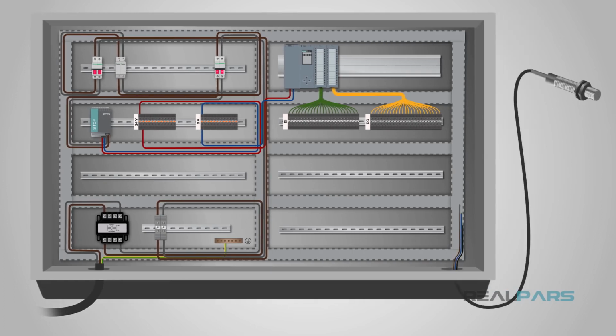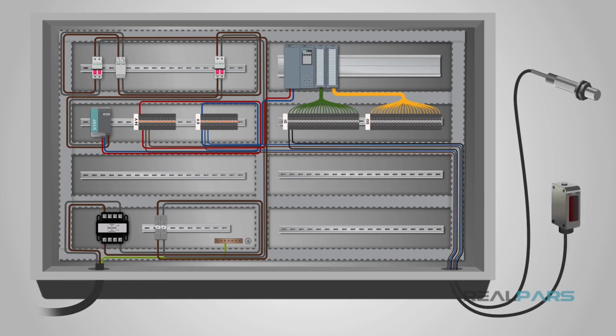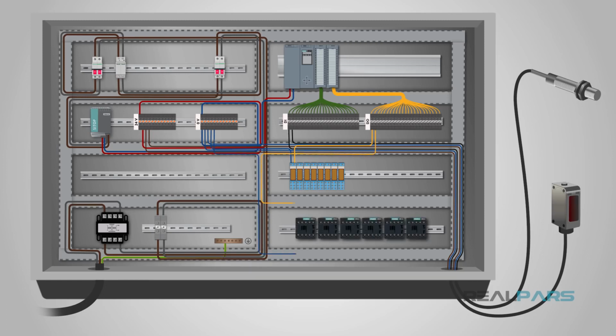Field devices, such as proximity switches, photo eyes, and other sensors, are set up on the assembly line to give the feedback needed for the PLC to control the operation of the line. The PLC outputs will be wired to a bank of relays that will close an internal contact that will send power out to turn on or off a device on the assembly line. Smaller relays will control devices such as lights or fans, while a bigger relay, called a contactor, is used to control motors.